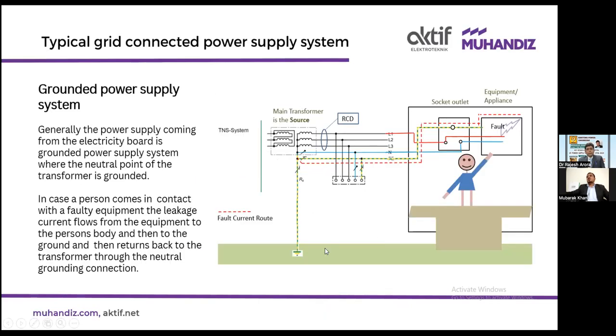Now I have just tried to show a typical grid connected power supply system, how it looks: TN, TNS system, TT system, whatever. I simply want to show a grounded power supply system where the transformer neutral is grounded. In this diagram, there is a main source transformer, and this transformer neutral point is grounded. Then neutral is given to the load side, and the earth conductor is also going from the neutral point to the load area. Suppose this is a distribution transformer near your complex, and this power is coming to your society.